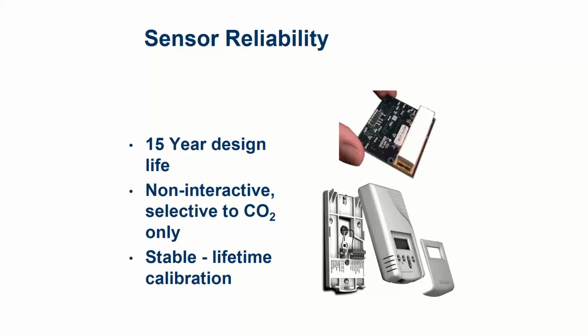If this thing's off by 50 parts per million, remember, we're controlling a giant, huge mechanical damper with an old crappy actuator with broken linkage. If I'm reading 1150 parts per million instead of 1100 parts per million, that's not the end of the world. If it's off by a couple hundred, okay, that's going to be a problem. It's got to be pretty close, right? Horseshoes and hand grenades kind of thing.